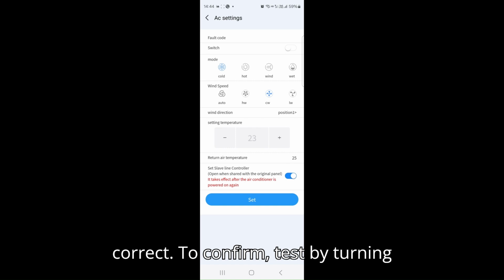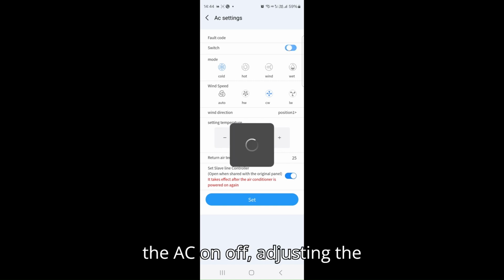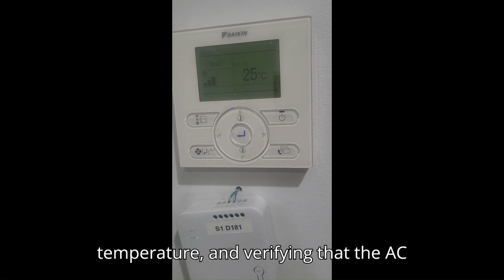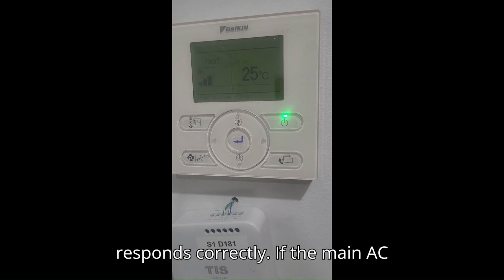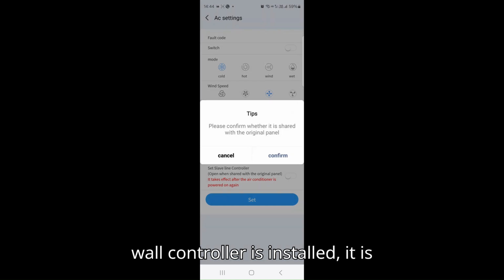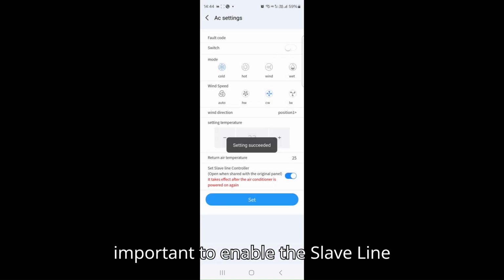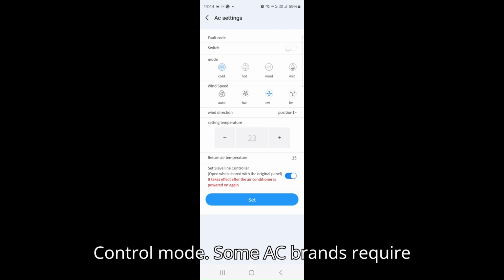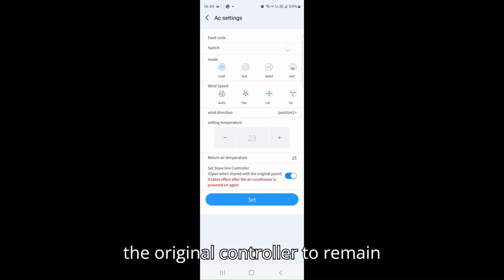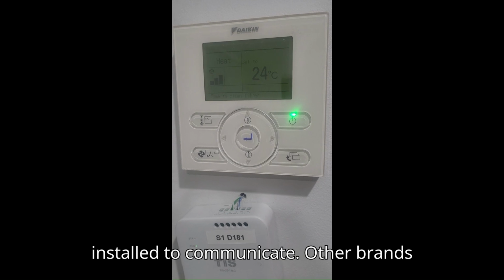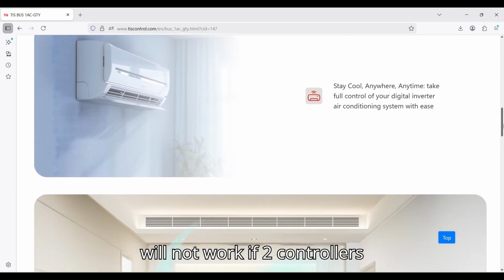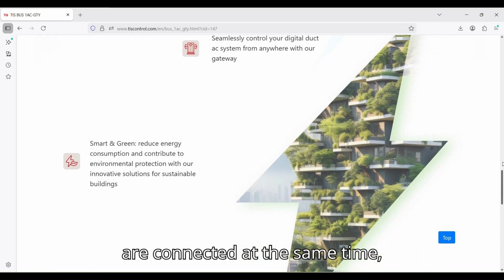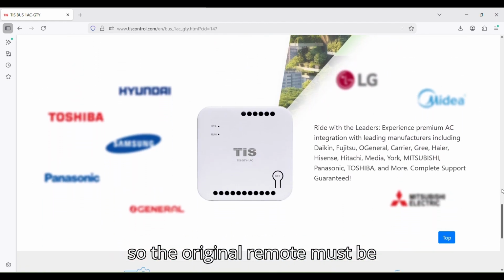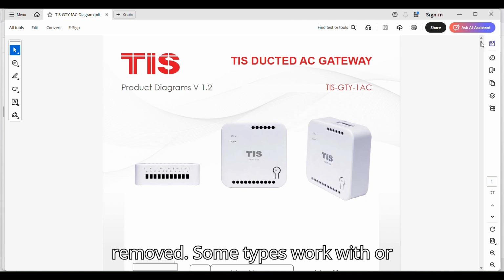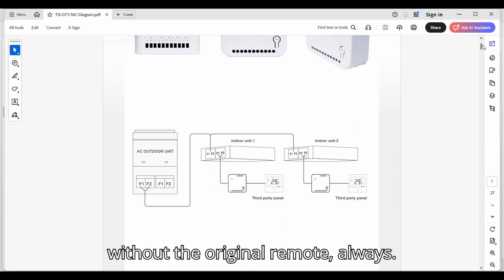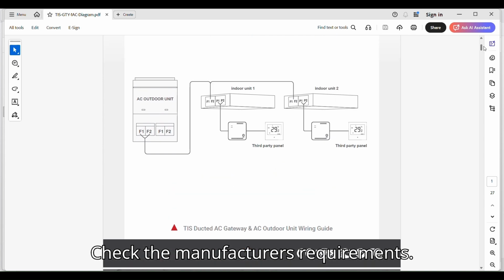To confirm, test by turning the AC on/off, adjusting the temperature, and verifying that the AC responds correctly. If the main AC wall controller is installed, it is important to enable the slave line controller mode. Some AC brands require the original controller to remain installed to communicate. Other brands will not work if two controllers are connected at the same time, so the original remote must be removed. Some types work with or without the original remote. Always check the manufacturer's requirements.